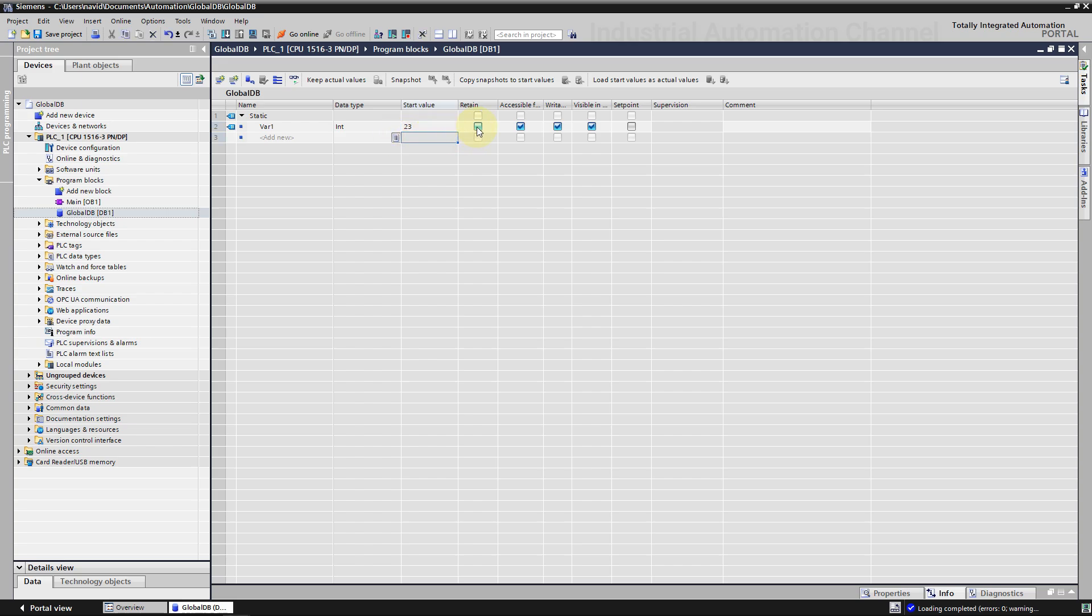To prevent data loss if the PLC stopped or there was a power failure, we can mark the data as retentive. This data will be stored in a retentive memory area and it will not be reset to the start value. Be careful, values of the retentive tags take the defined start value only after a cold restart. After a warm restart they retain their values and are not reset to the start value.